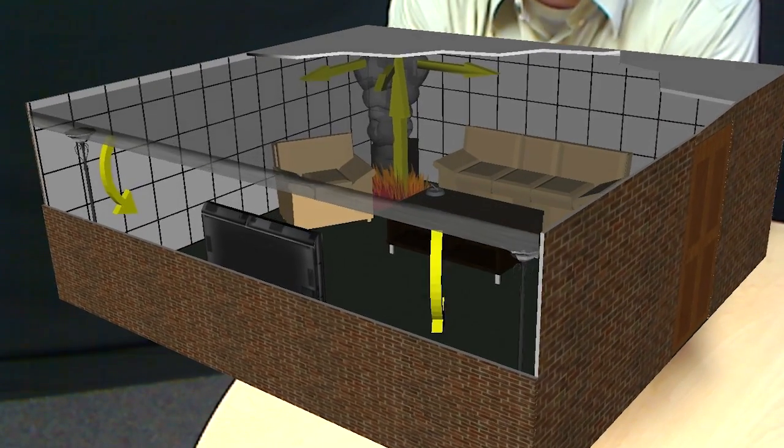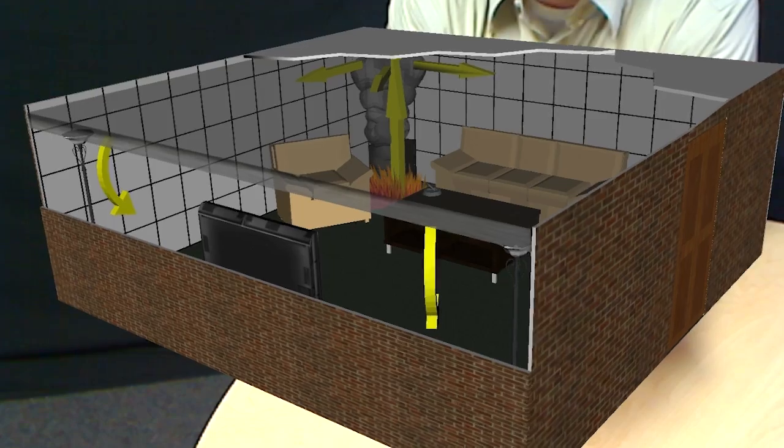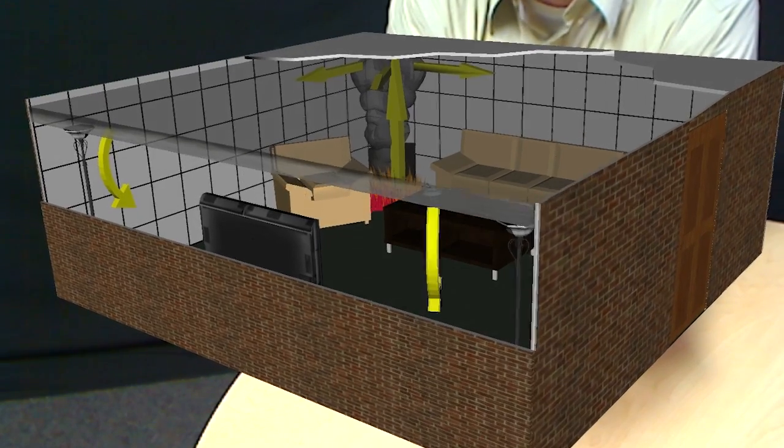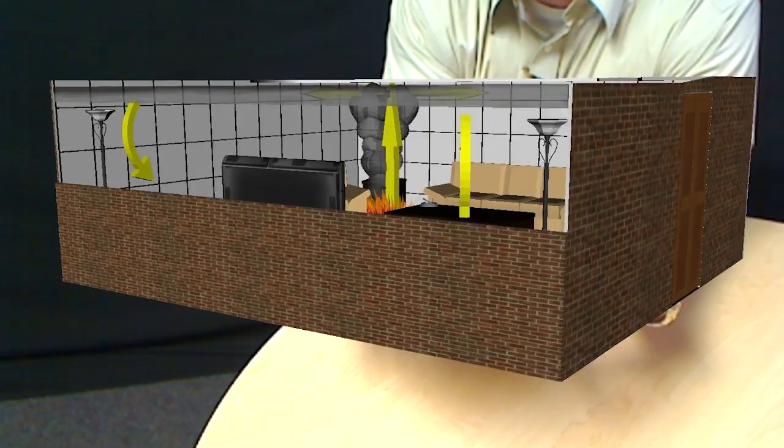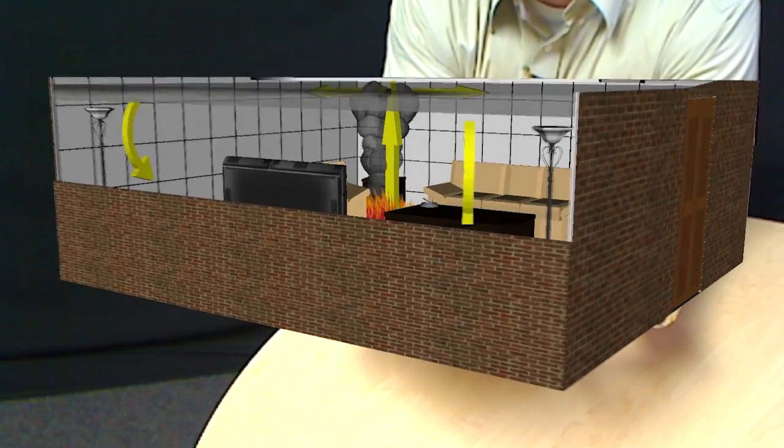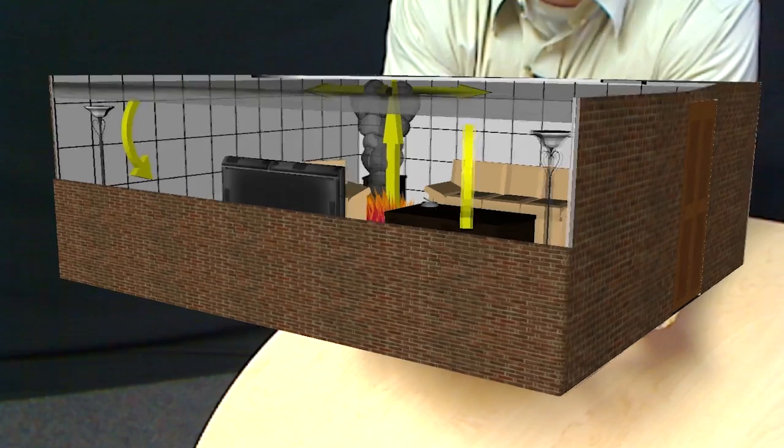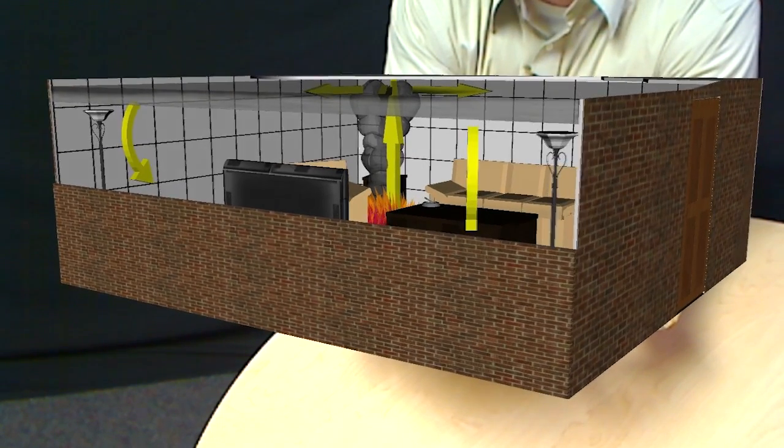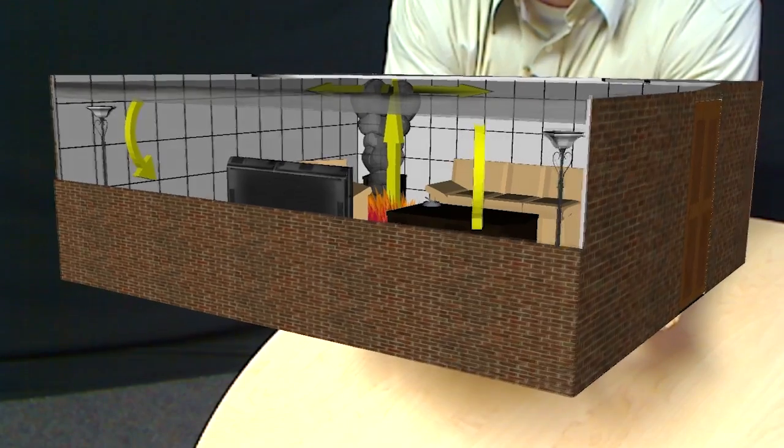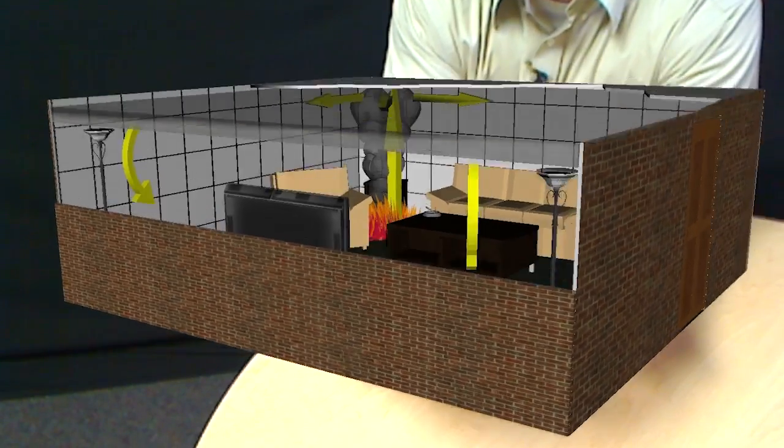And because the smoke will follow the path of least resistance, in this case, the least resistance will be down into the compartment. So we can start seeing this distinct difference between the heated gases in the upper layer—what's termed the upper layer—that collection of smoke and heated gases near the ceiling, start to develop and descend from the ceiling.